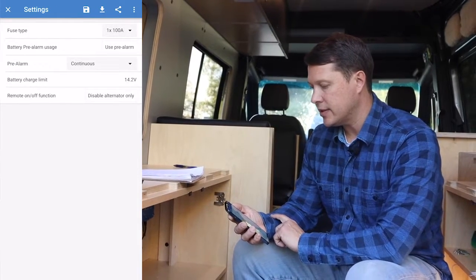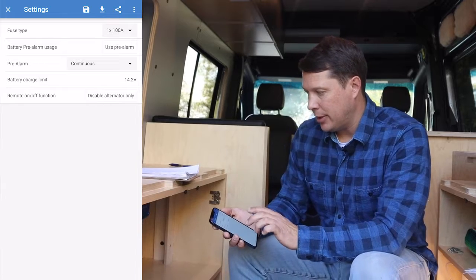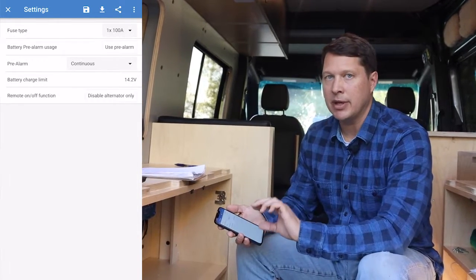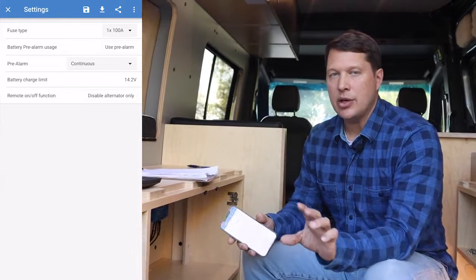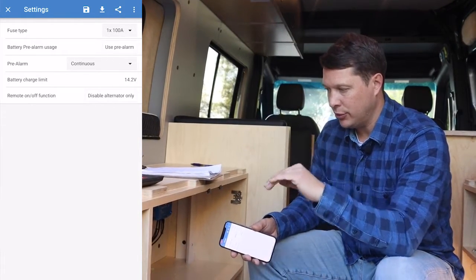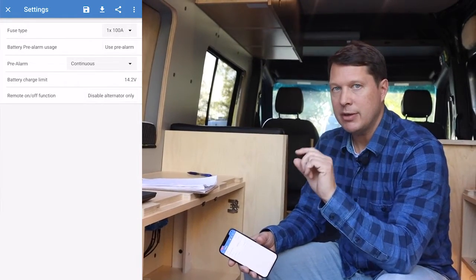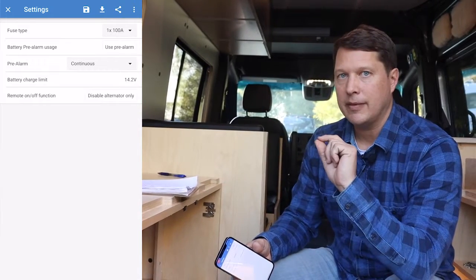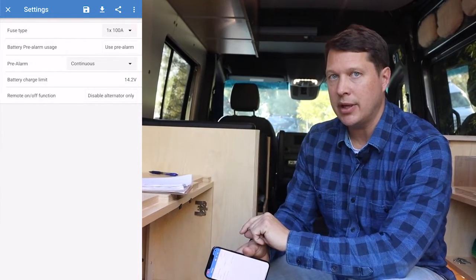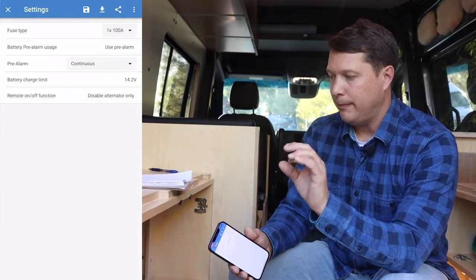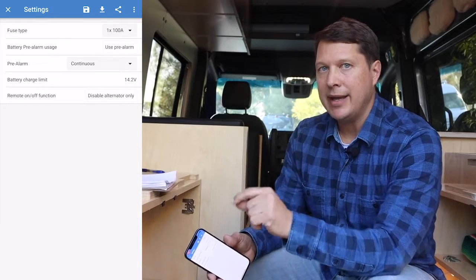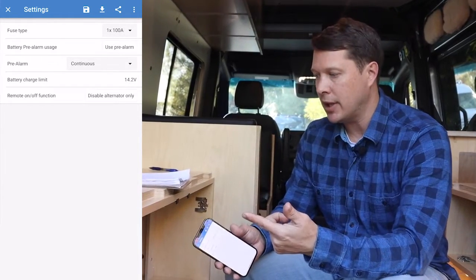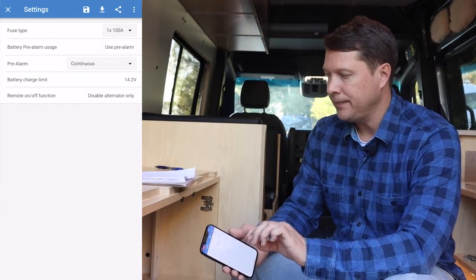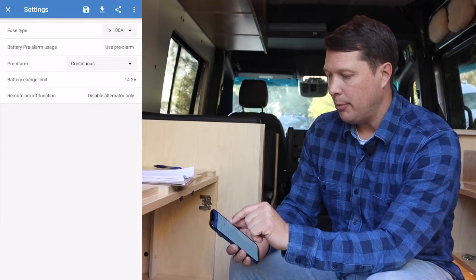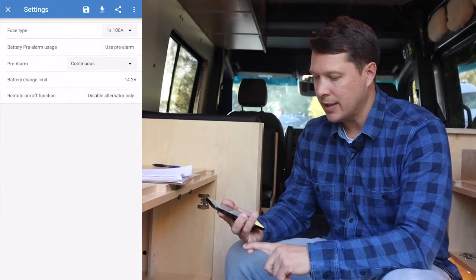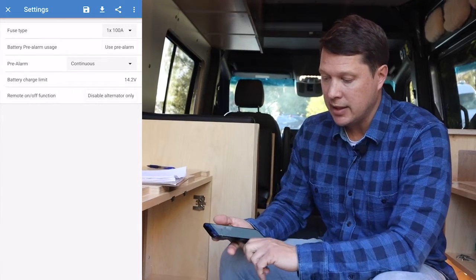But if we jump into the settings, then we need to set the fuse type. And without setting the fuse type, this piece of equipment will not work. And just so you guys know, the amount of power that can potentially come through into the batteries is determined by the size of the fuse. So out of the box, this will include a 100 amp fuse, and just by the programming, it will allow about 90% of that number to potentially come through the line. So we could be getting up to 90 amps of charging through the CL unit, but that also is dependent upon a couple other things like the temperature of the batteries and also the impedance in the line.